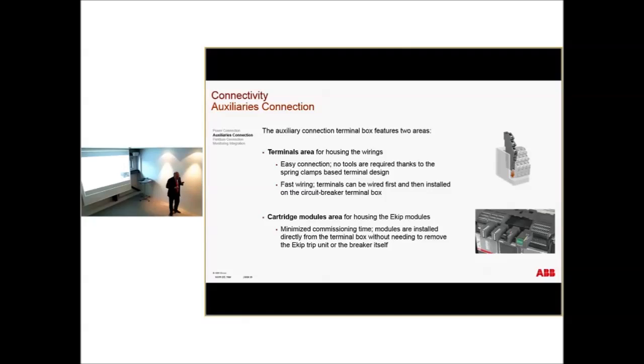So basically, what we have done is move these modules from the moving portion to the fixed portion. Communication, for instance, is permanent. So you can take out the breaker, and it communicates that the breaker is not in, but the communication continues. Here you see that the cartridges are now installed on the fixed portion.